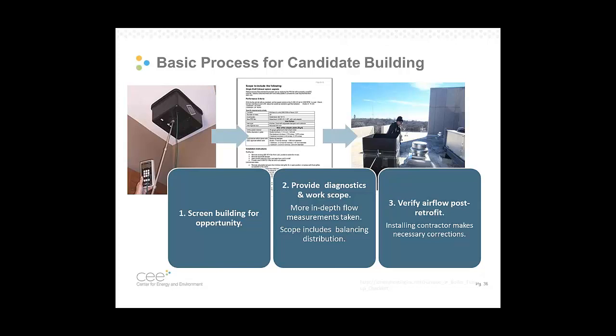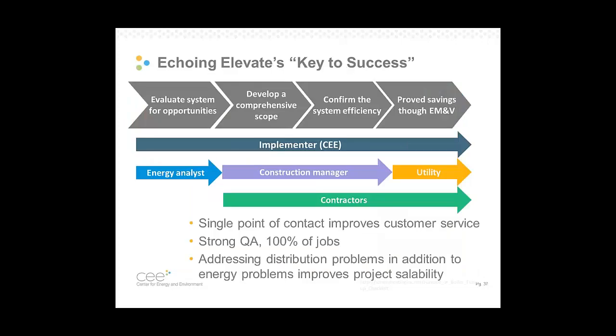The way this process is working into our multifamily programs here is that we're screening the building for the opportunity at our audit, which in Minnesota is free to building owners, so they get a free energy audit. That's where we're doing this ventilation screening, and we're trying to determine whether there is an energy saving opportunity or not. If there is, we're recommending that they go into more detail, getting some more diagnostic work and a work scope written up, and we're providing that service as well. We're taking more in-depth flow measurements and determining how to save energy and then solve their distribution issues. And we're also verifying the airflow post retrofit. After the contractor commissions the airflow, we're coming and checking on the commissioning just to make sure it is within design parameters.